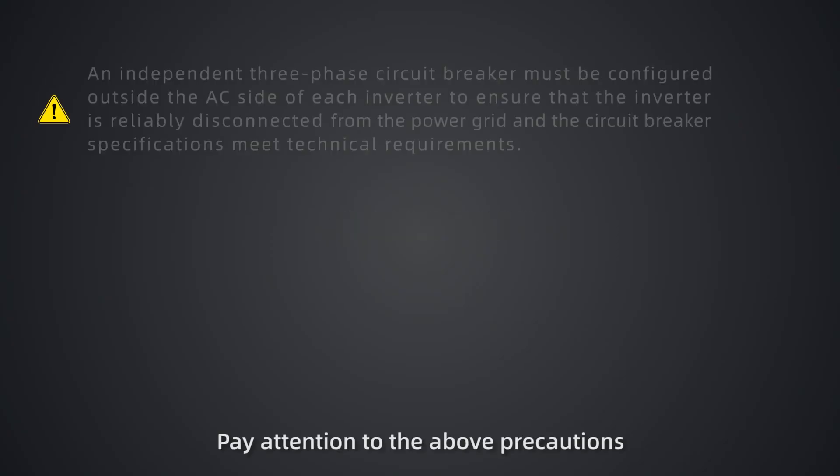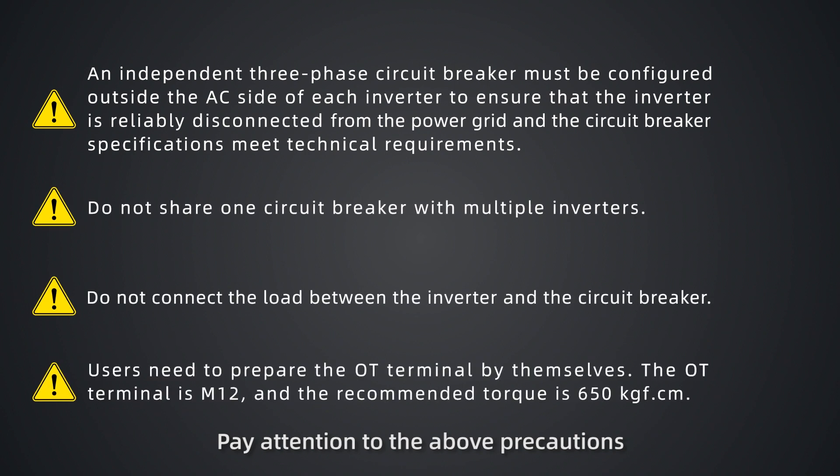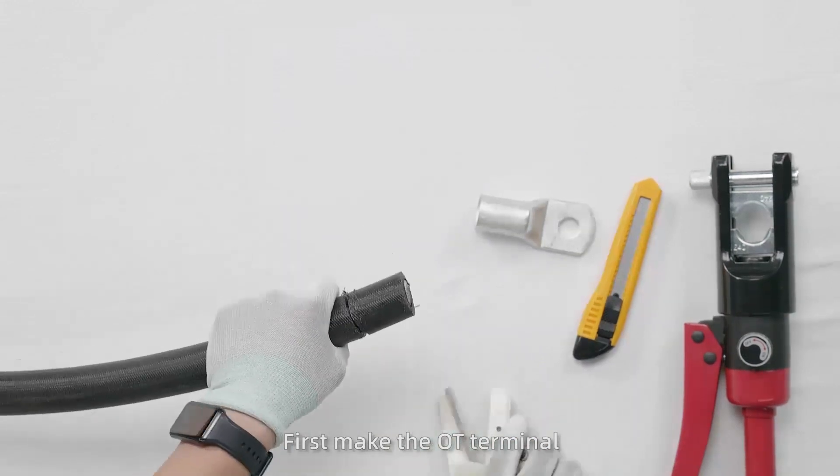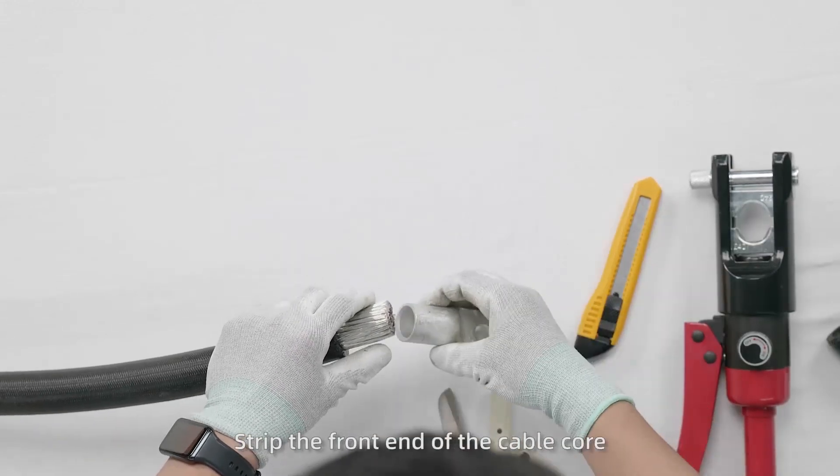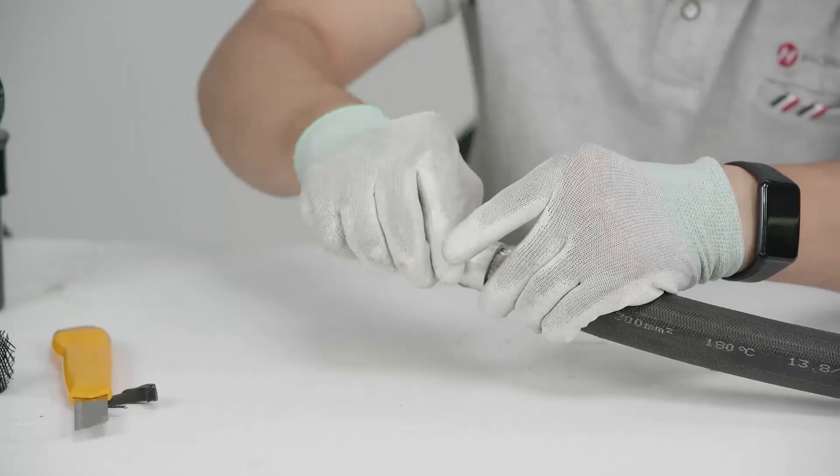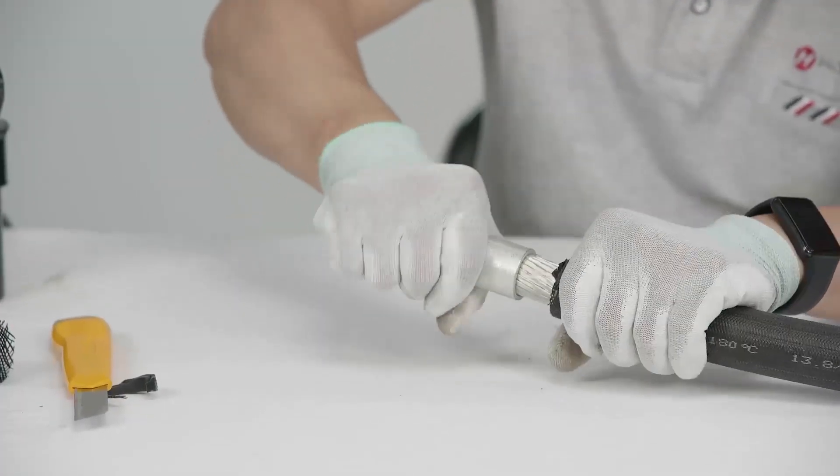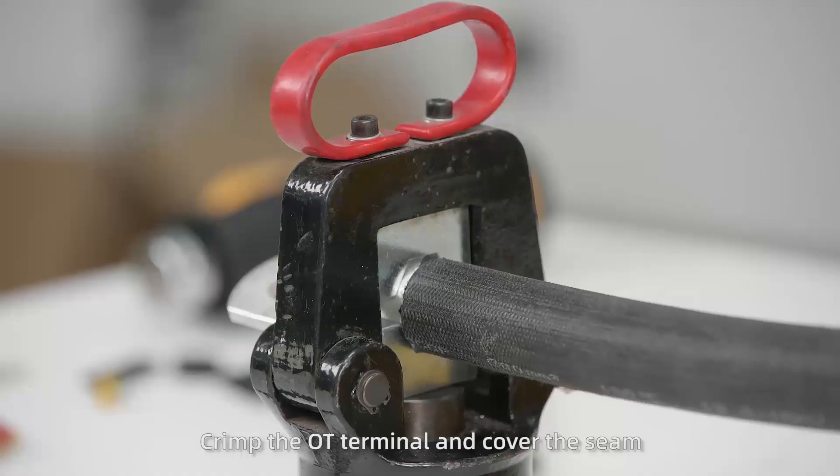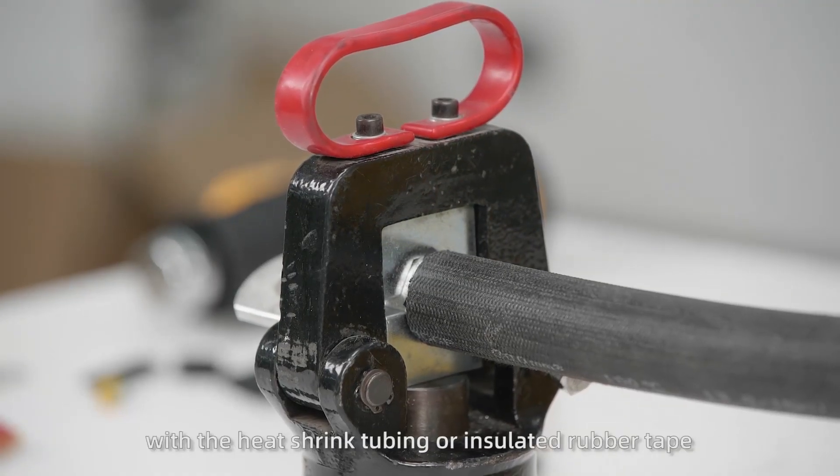Then, connect cables on the AC side. Pay attention to the above precautions before cable connection on the AC side. First, make the OT terminal. Strip the front end of the cable core. Crimp the OT terminal, and cover the seam with the heat shrink tubing or insulated rubber tape.